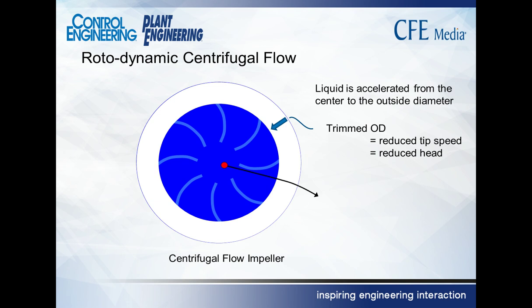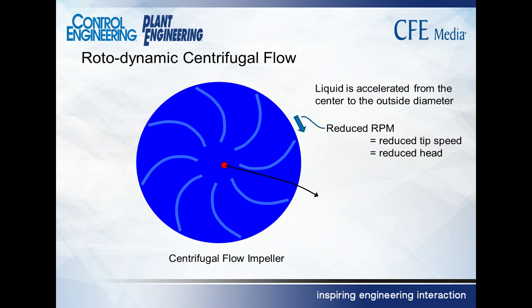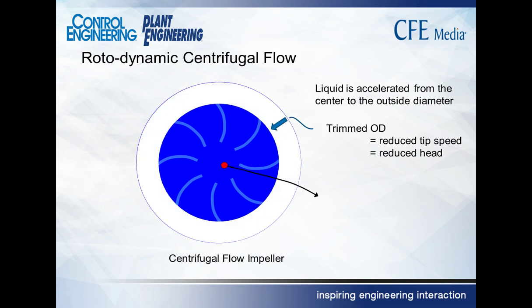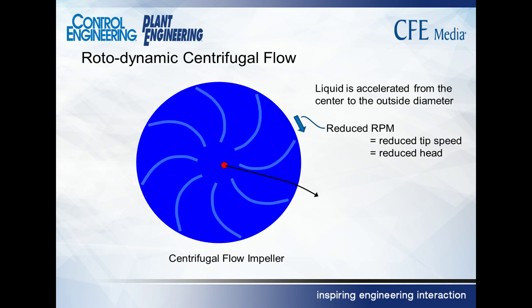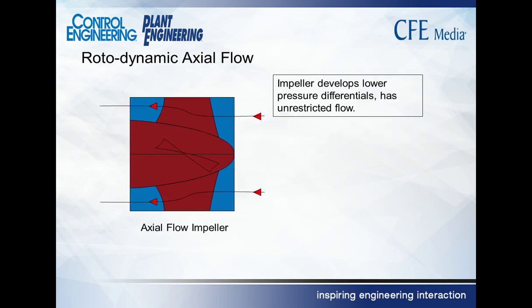Another way of reducing that tip speed and reducing the flow and head through the pump is to reduce the rotating speed without having to trim the impeller. So whether you trim the impeller to a smaller diameter or leave the impeller at its full diameter and run it at a slower speed, the effect is very, very similar, in fact, virtually identical. So either method can be used for adjusting the capacity of a pump.